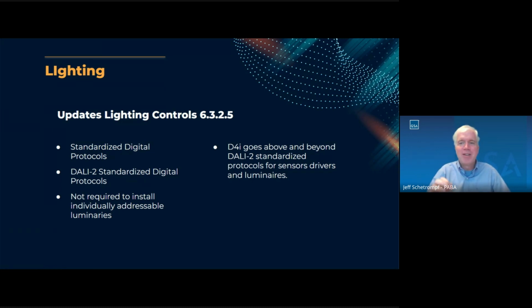But DALI 2 addresses the problems that we ran into with the previous version of DALI. It addresses those proprietary control problems. It lets us deal with systems where the manufacturer may no longer exist. There's a way out. They probably should have called it something other than DALI as a marketing strategy, but DALI 2 is what they called it. D4i is shorthand for DALI for the Internet of Things, DALI for IoT. It's an extension of the DALI 2 protocol that enables LED luminaires to interact with control devices, such as sensors, in the external control network. A typical example is a sensor on the lighting fixture itself that controls both the lighting and the HVAC for that space.